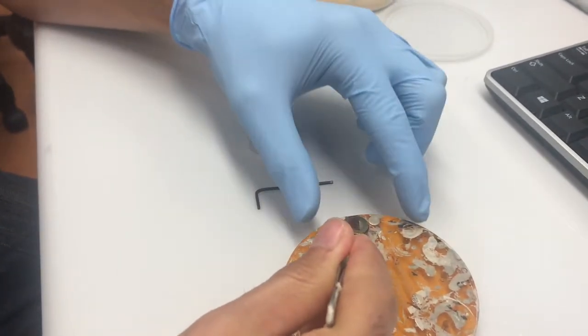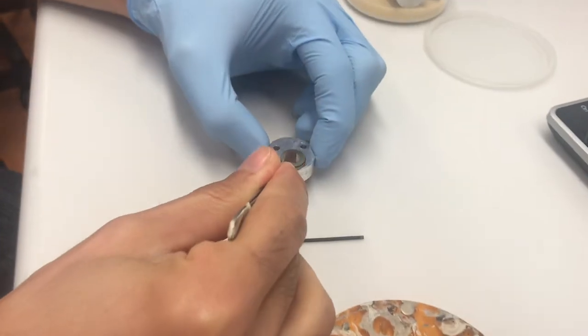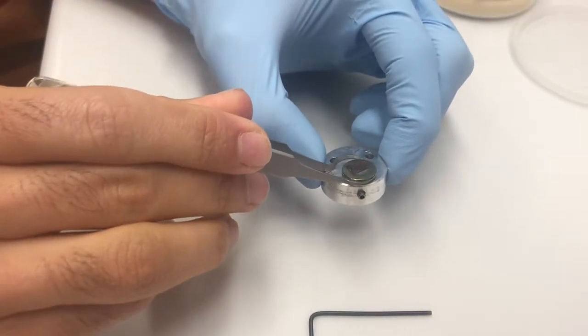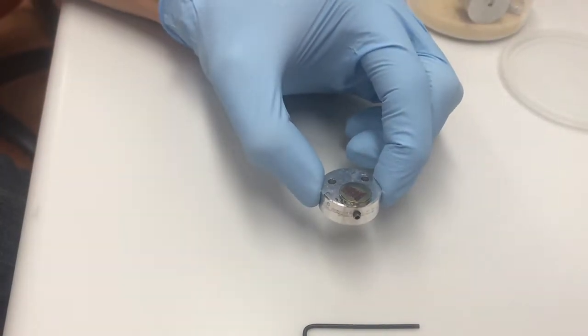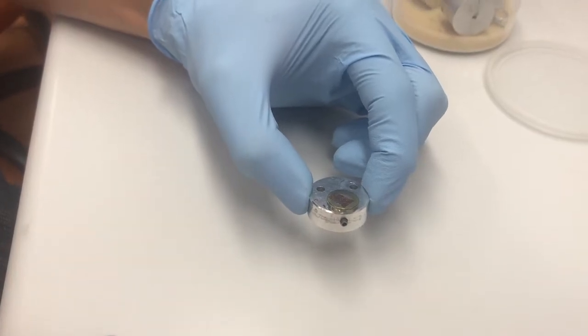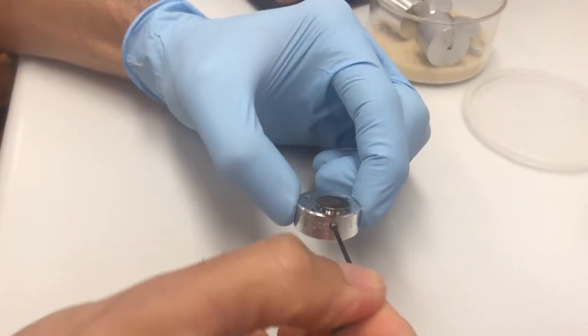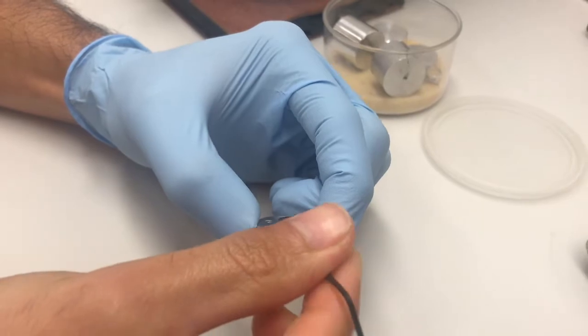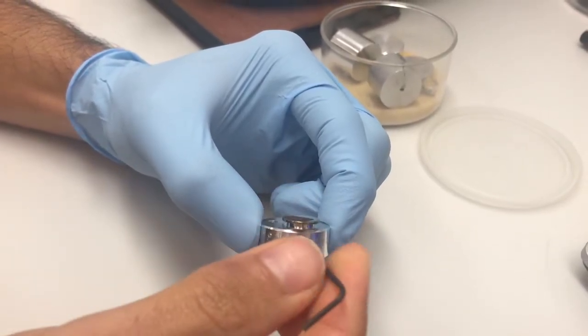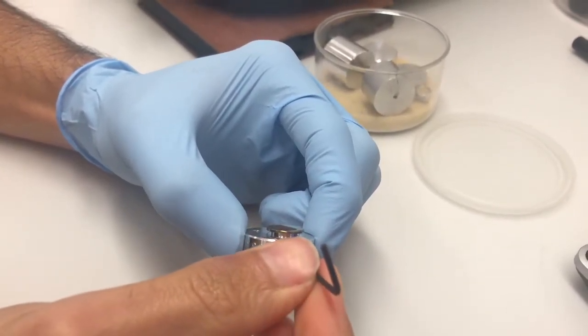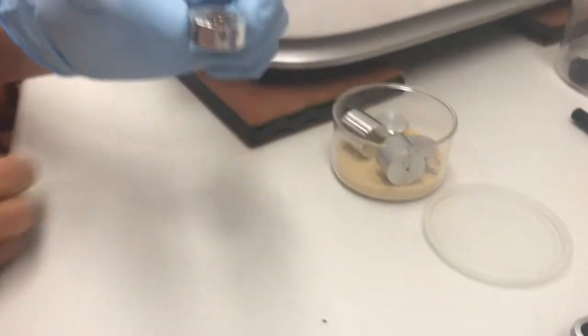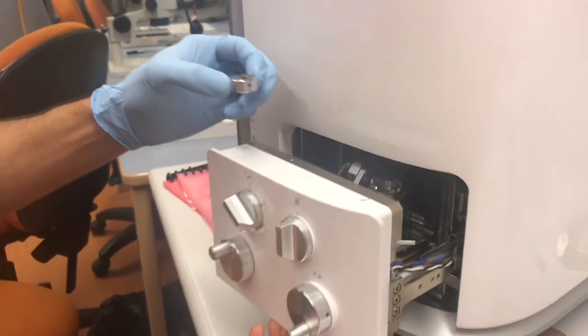Carefully pick up your sample using a pair of tweezers and place it into the sample holder. Secure the sample by gently tightening the hex socket, being careful not to over-tighten. The sample is now ready to be placed in the SEM chamber.